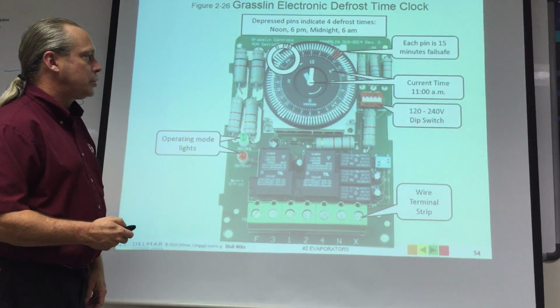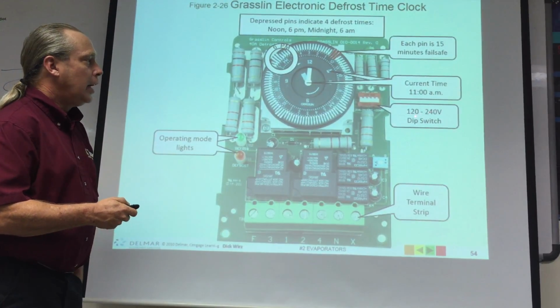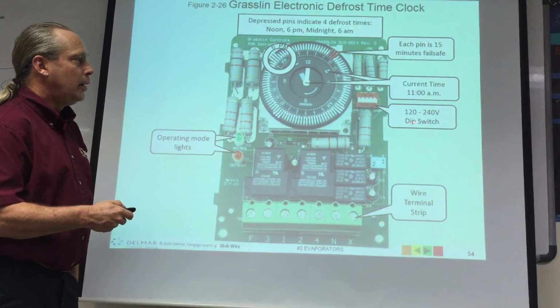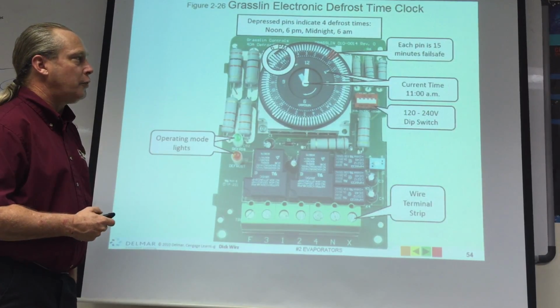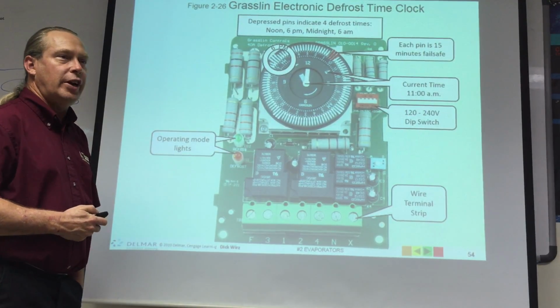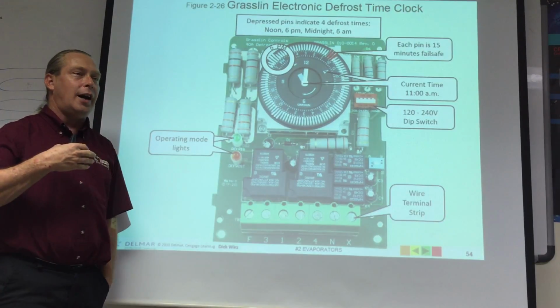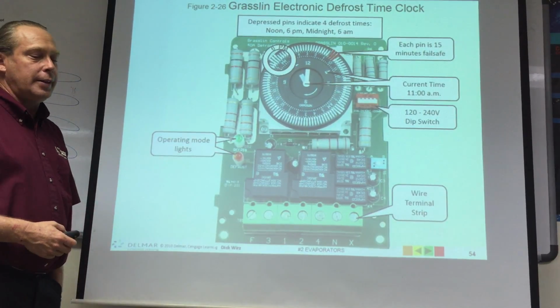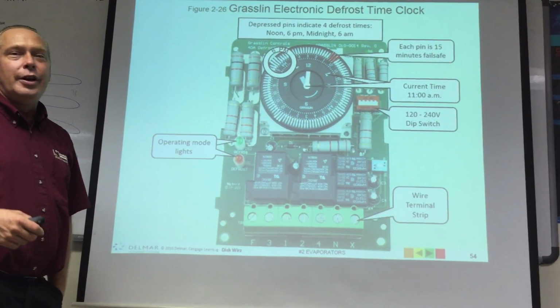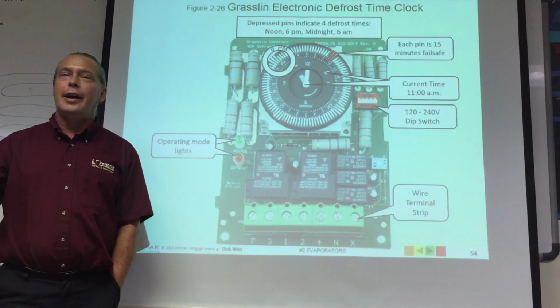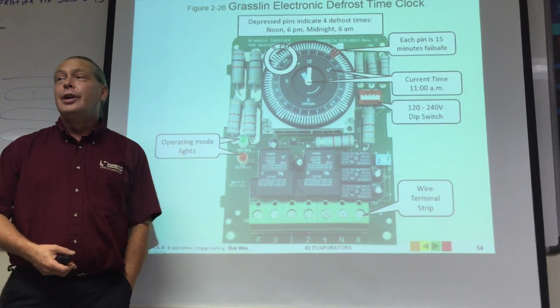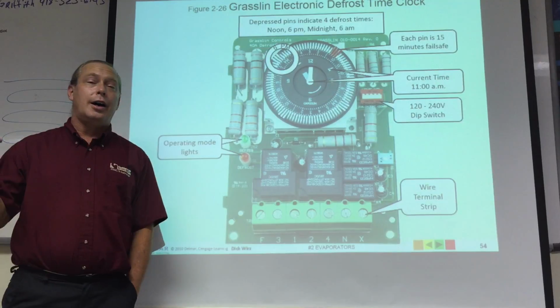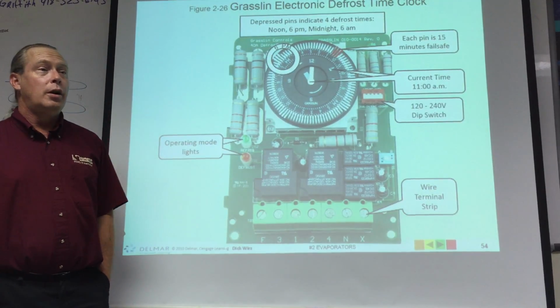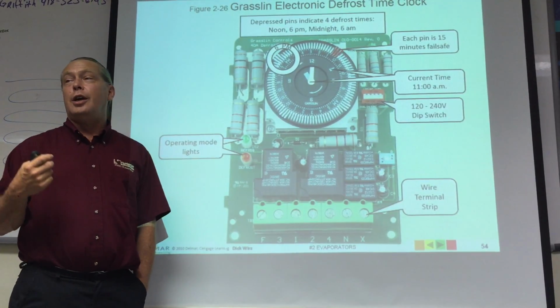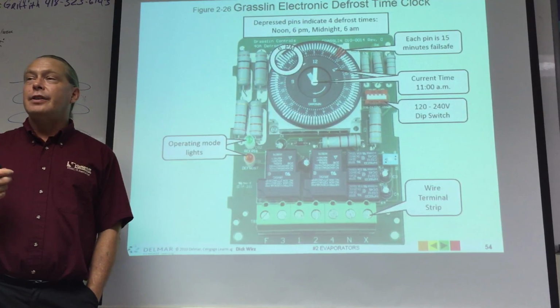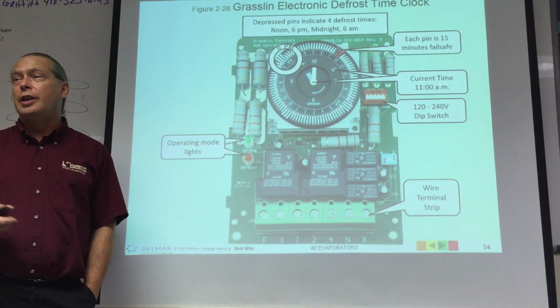Easy wiring terminal strip compared to the old school. And this will switch right here between 120 and 240 volts. So it has a lot of uses. You could see this as a defrost timer. You could see it inside an irrigation timer. You could see it controlling an entire chiller system or an entire boiler system. You might even see it as the time clock for parking lot lights.